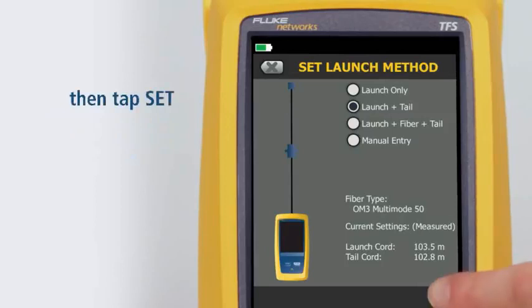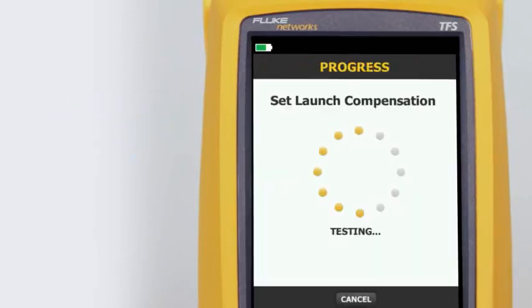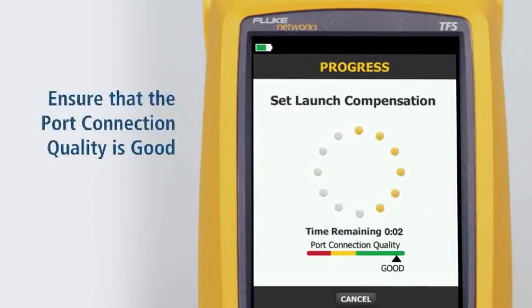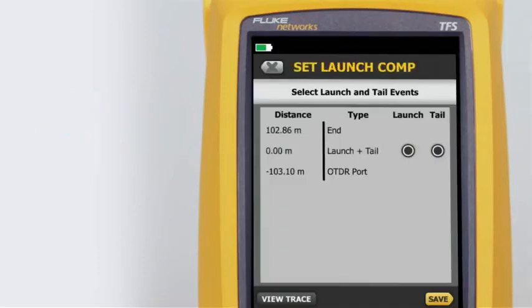The tester will analyze the launch and tail cord properties. Ensure that the port connection quality is good. The connection between the launch and tail cords is both the launch and tail event, because we've connected the two cords together.